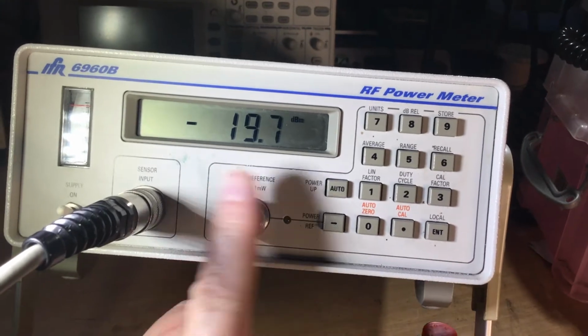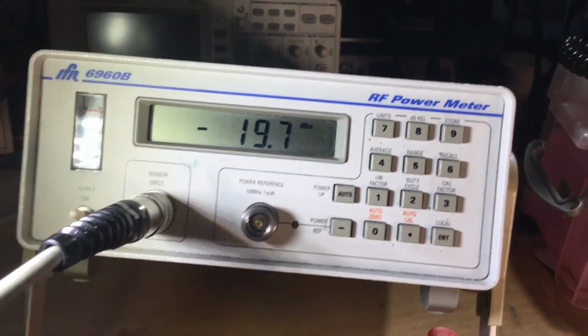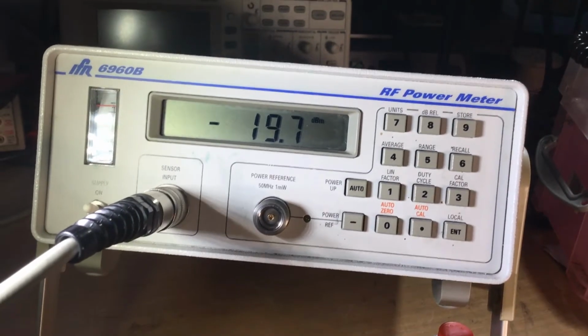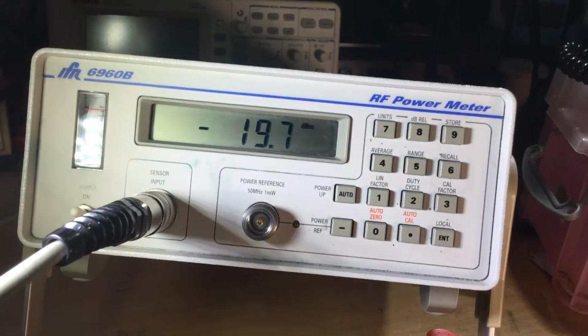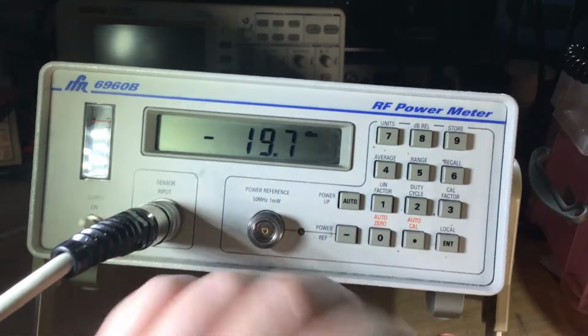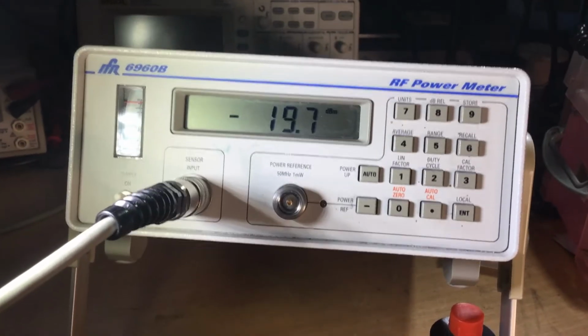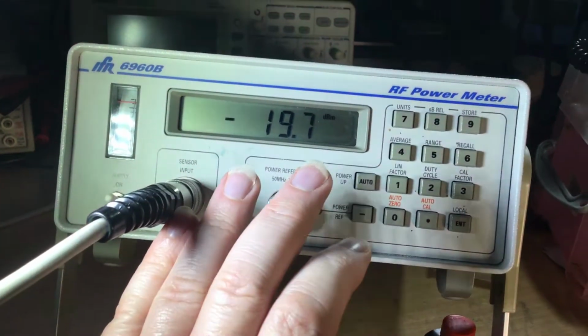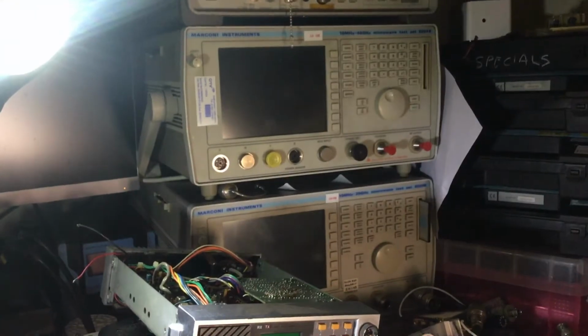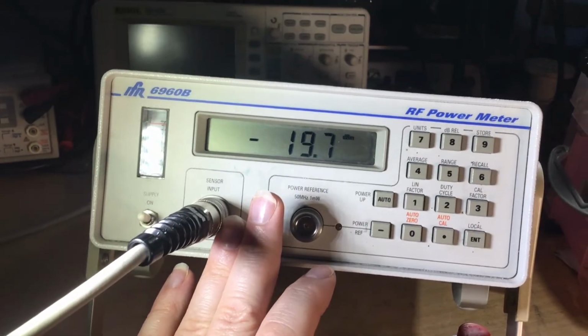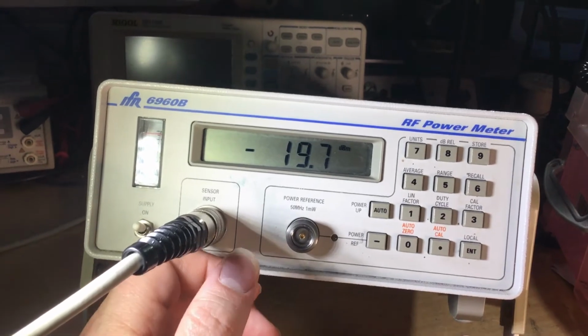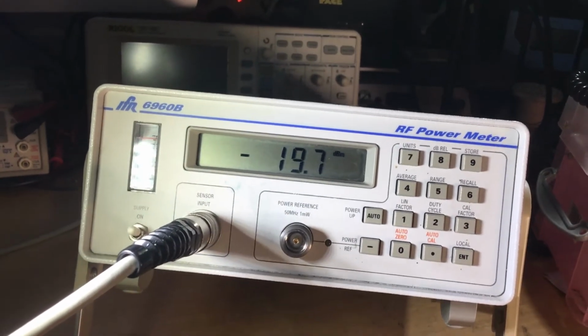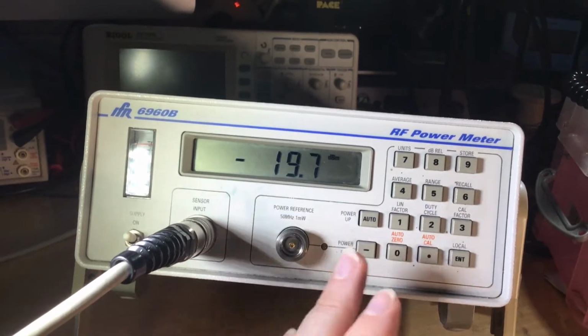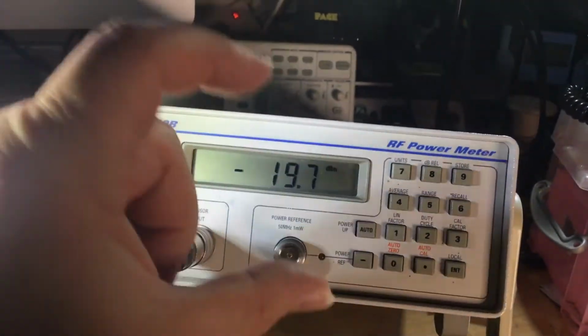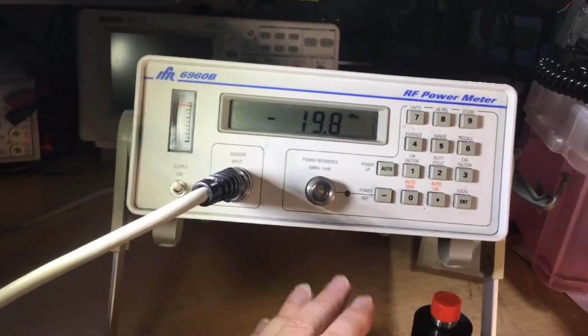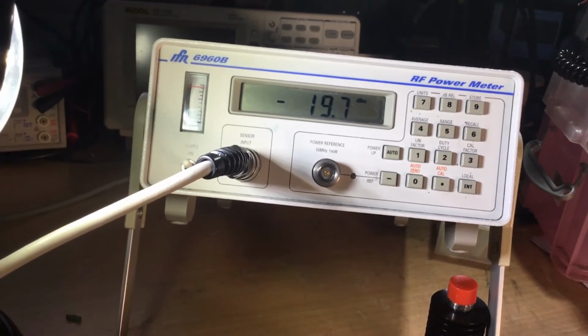It'll still read accurately with the calibration here, but for super accuracy, as per the calibration house that calibrated the sensor, you enter the data in here, and then the finer calibration detail is held within its EEPROM. Now on the other range of test sets, microwave test sets such as these here, they remember the sensor that's connected in. There's a little EEPROM in the sensor that talks to this, and you can get it to remember the calibration data for different sensors, so you're not entering in all the table each time you're using it. So that's quite an advantage as well. So they're quite clever in that sense.